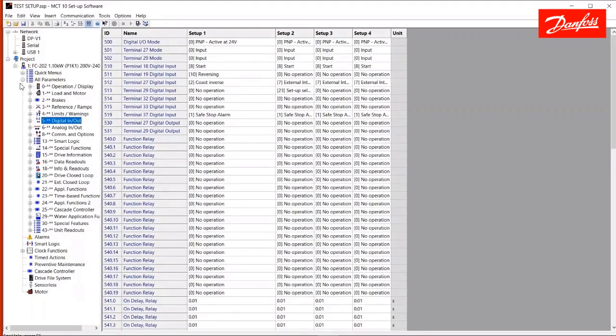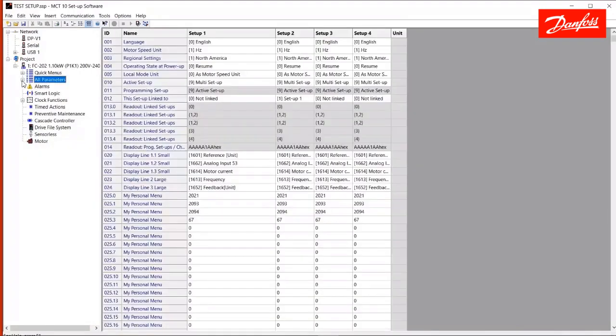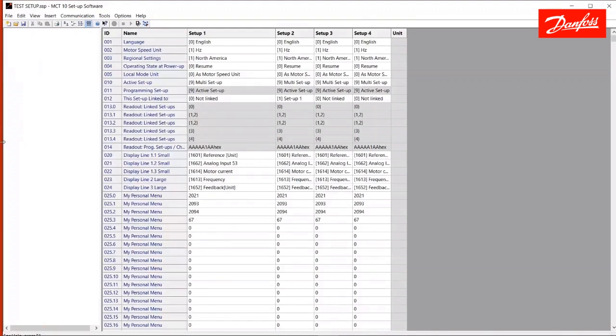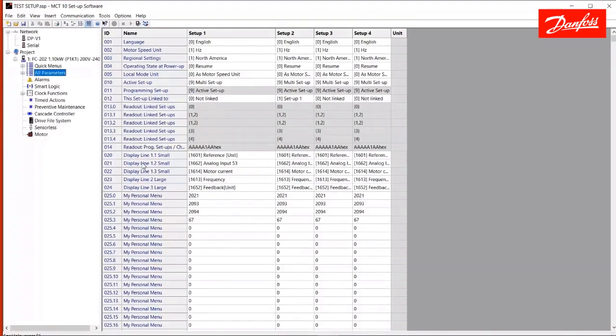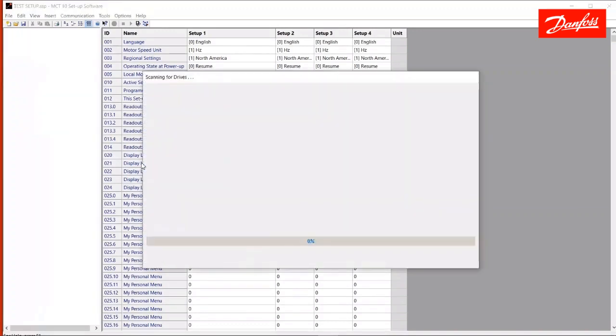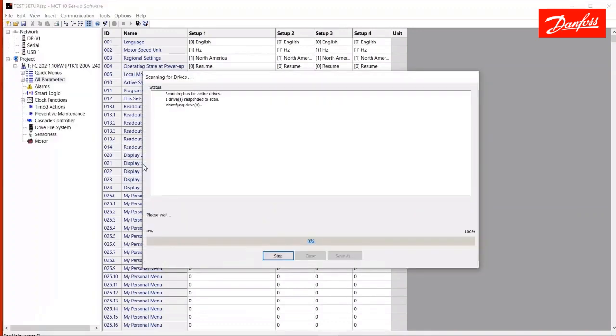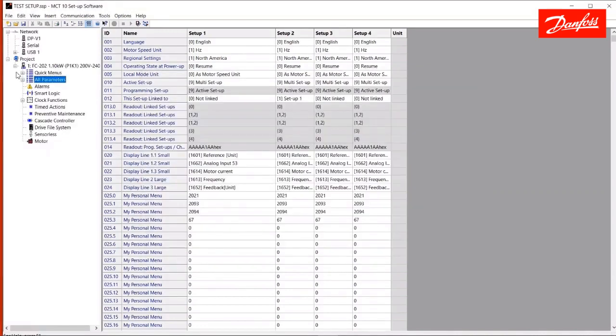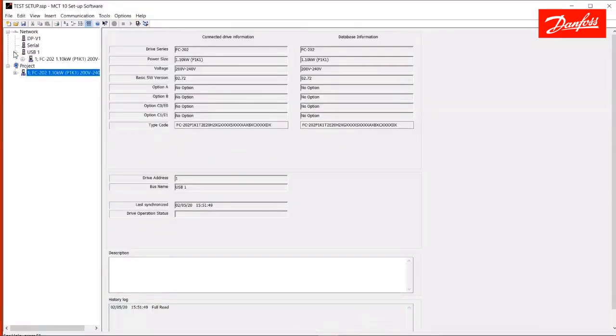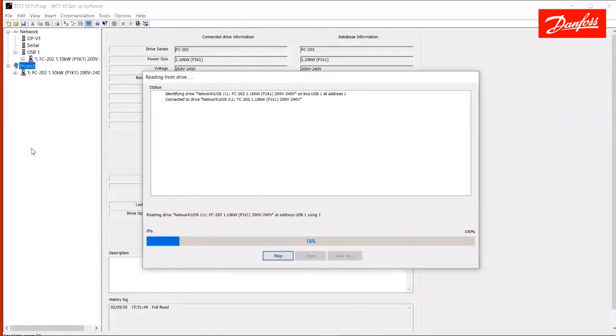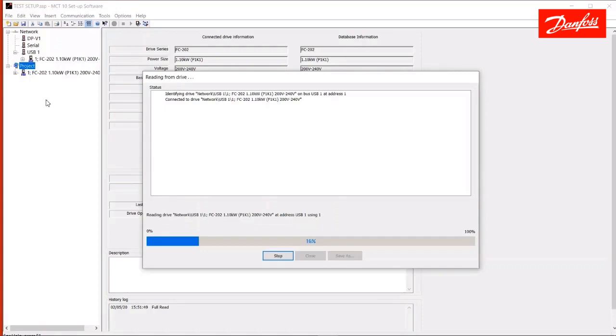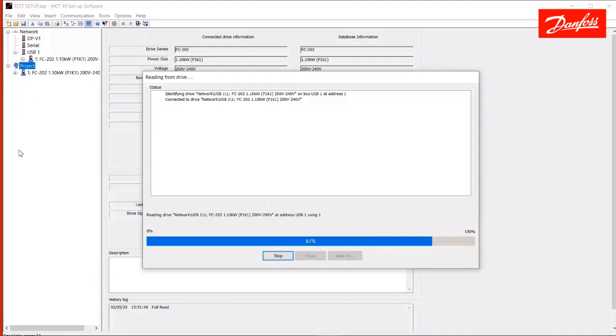If I had multiple drives of interest in the project, I will disconnect from the live drive, approach the next drive of interest I want to back up, and then plug it back in to that drive. And I would go through the same process here. I'm just going to go ahead and take the live drive and pull it down to the project side. Now I'll have two drives in the project. That is one limitation of the basic version. It will only allow you to put four drives in a project. You can save and create multiple project files, but each can only contain four drives. With the paid version, or the licensed version, it will allow you to put up to 126 drives in one project.